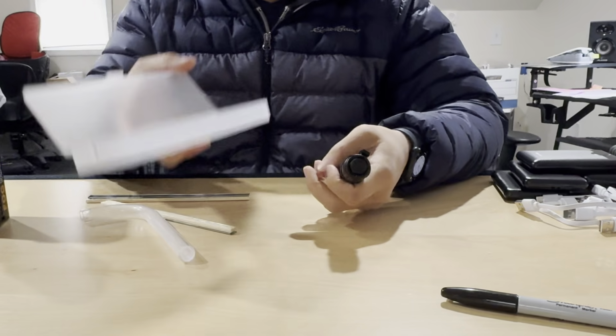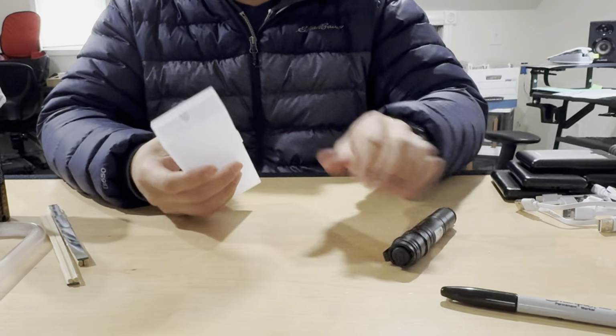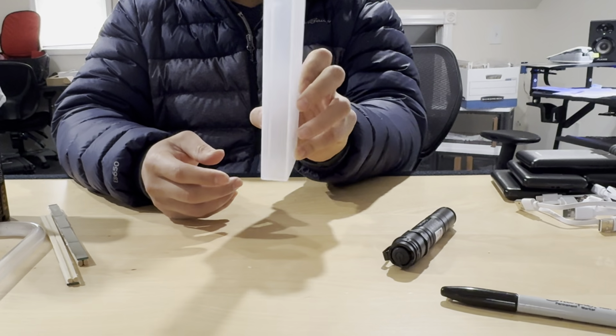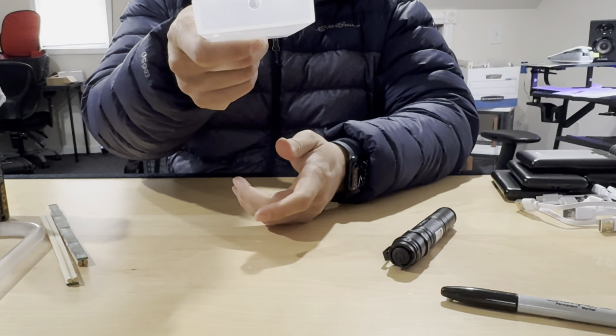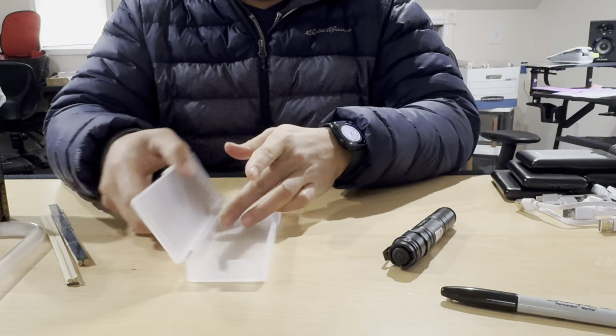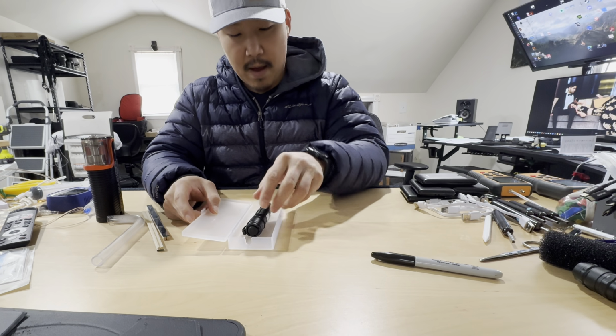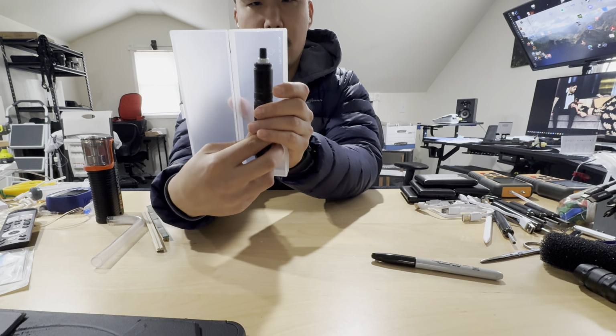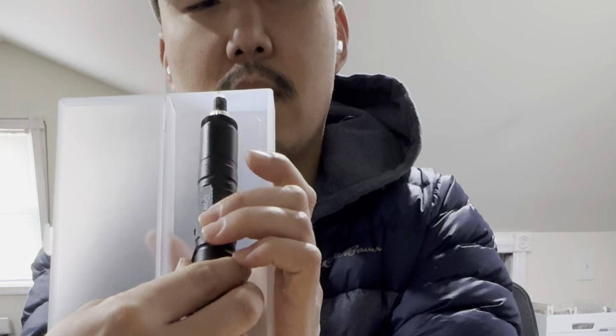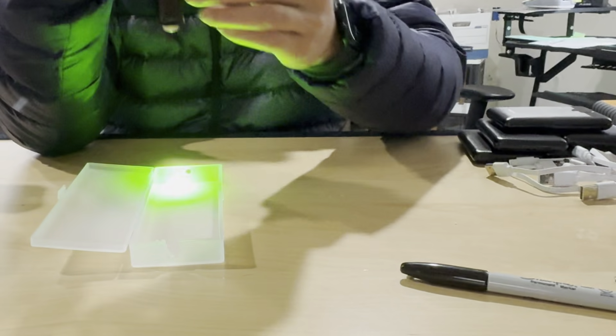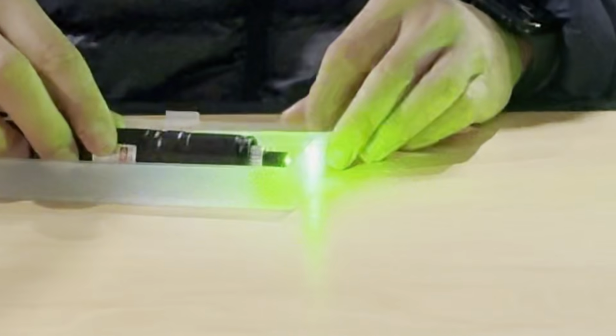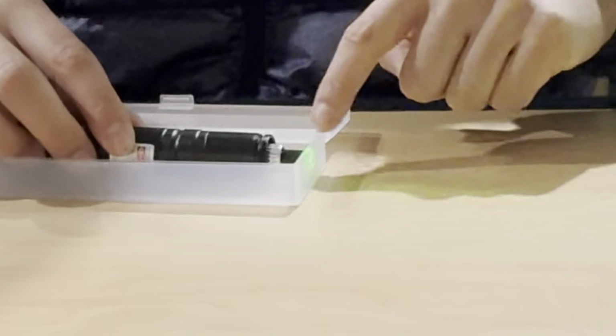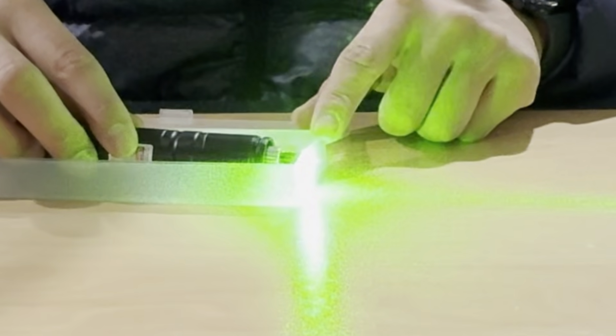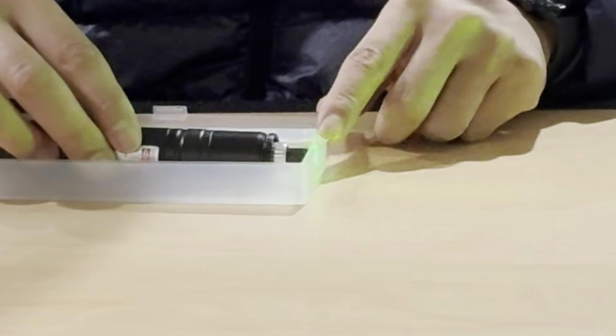What I would like you to do is, we have 5 lasers and 5 boxes. These boxes are to simulate the flat surface of a probe, okay? There will be a hole in each one of them, and they're going to be measured out and cut to match the hole in the box with the laser. So match the laser and the hole so that you do not see the light illuminating the box. If the light is illuminating the box, then it's not positioned correctly. It must not illuminate the box.